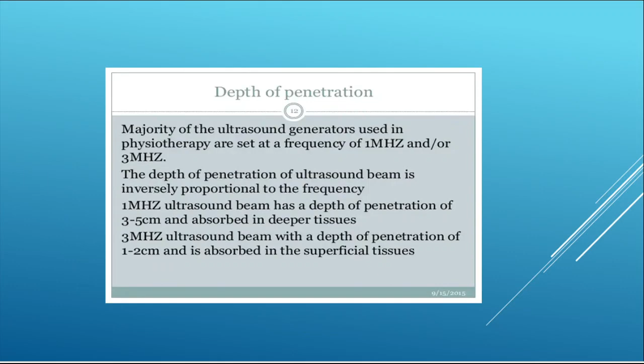Now, next is the depth of penetration. The majority of the ultrasound generators used in physiotherapy are set at a frequency of 1 megahertz or 3 megahertz. The depth is like that. The 1 megahertz ultrasound beam has a depth of penetration of 3 to 5 centimeters, as we have discussed in the previous slides, for the deeper tissues. 3 megahertz has a depth of penetration of 1 to 2 centimeters, and this is absorbed in the superficial tissue.